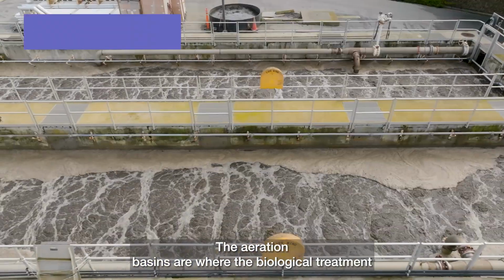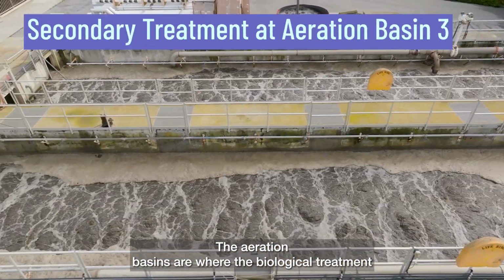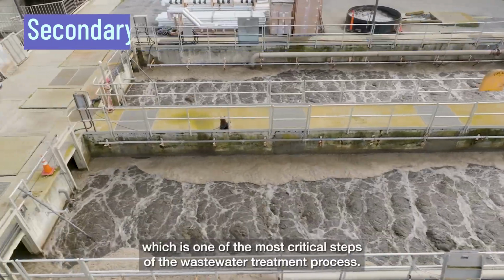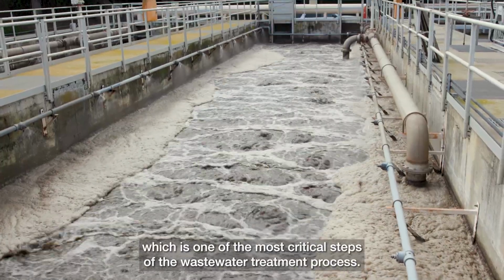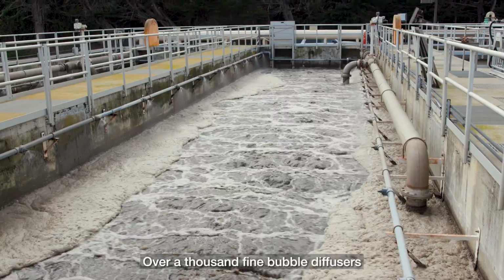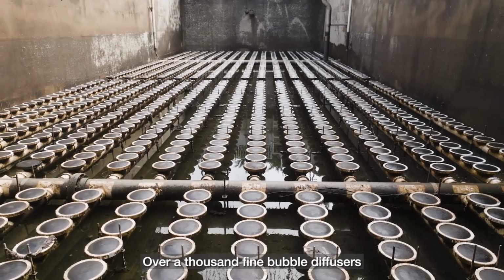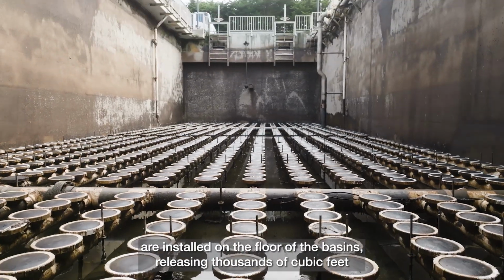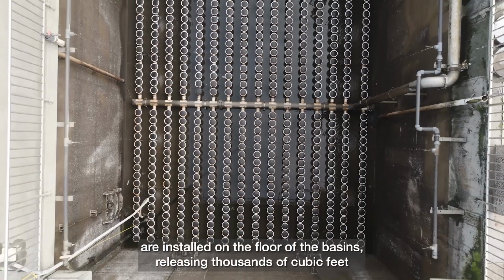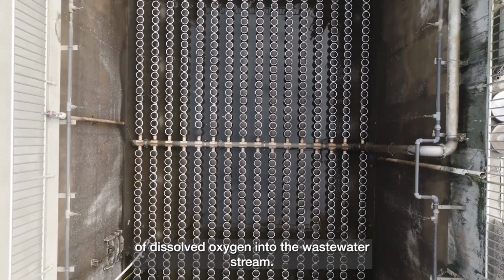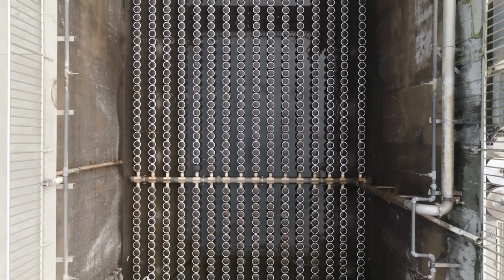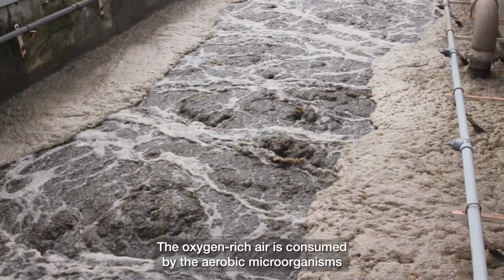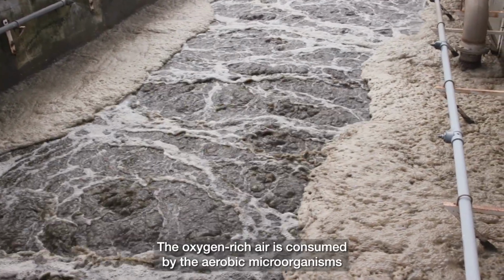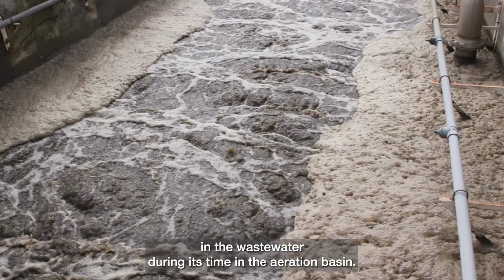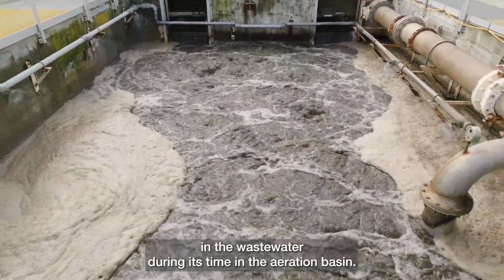The aeration basins are where the biological treatment of wastewater happens, which is one of the most critical steps of the wastewater treatment process. Over 1,000 fine bubble diffusers are installed on the floor of the basins, releasing thousands of cubic feet of dissolved oxygen into the wastewater stream. The oxygen-rich air is consumed by the aerobic microorganisms in the wastewater during its time in the aeration basin.